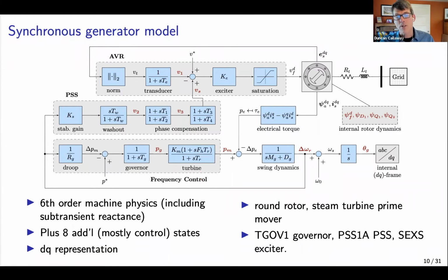We've got what's called an automatic voltage regulator. If you've studied generators, you've learned that if you adjust the magnetic field strength on your rotor, then you can adjust the voltage output of the device. And so this automatic voltage regulator is the thing that's trying to set what the grid coupled voltage is for that synchronous machine by adjusting its rotor magnetic field strength.